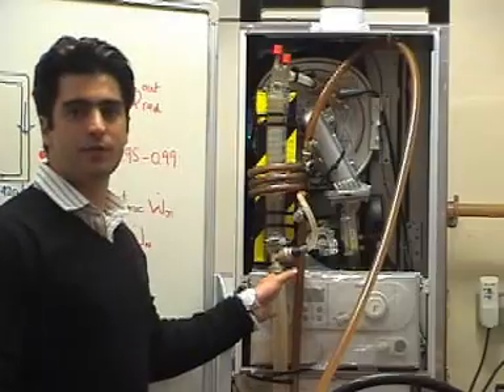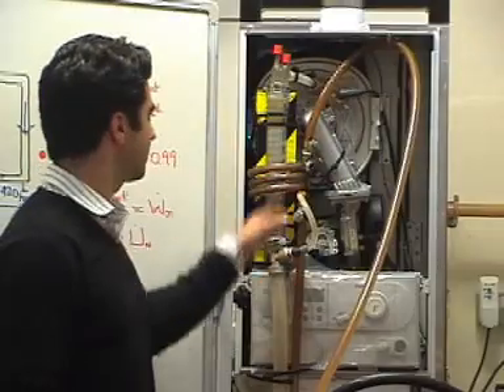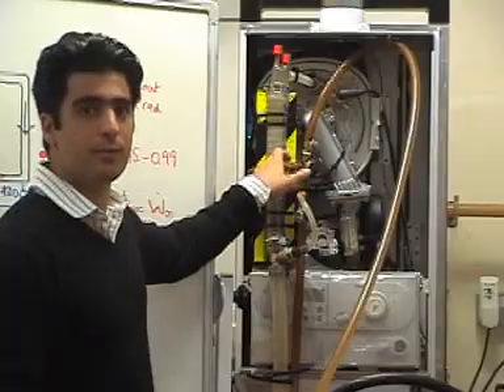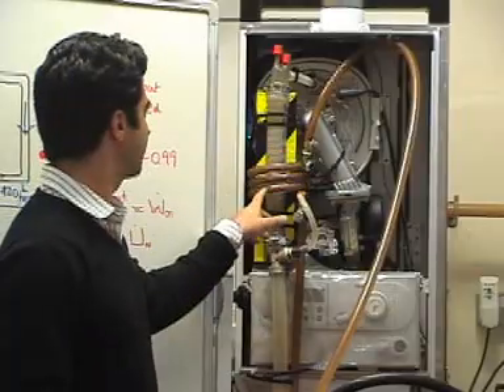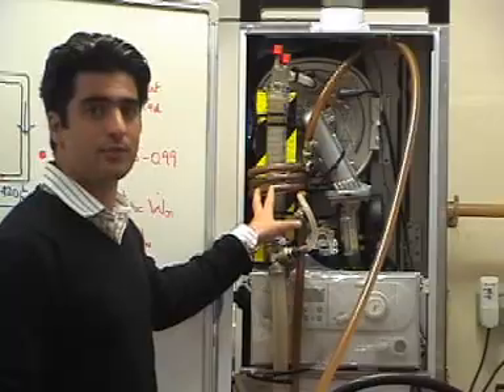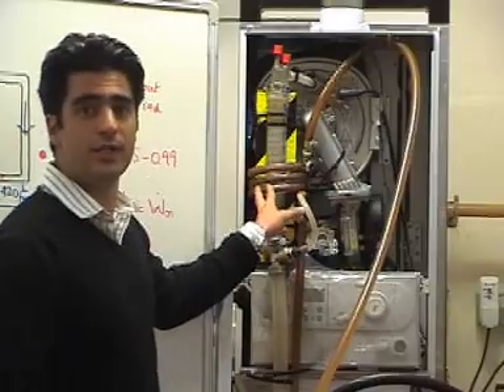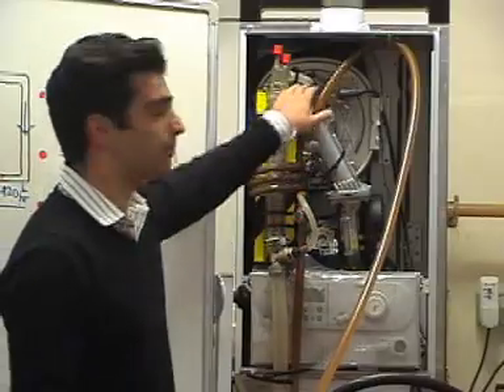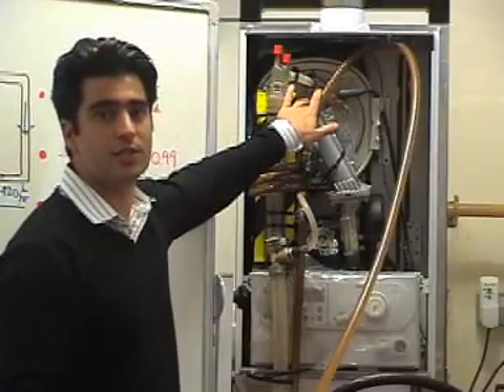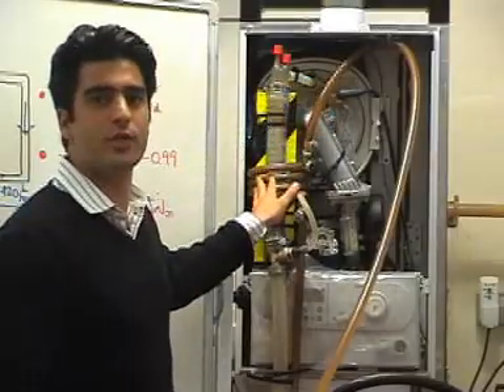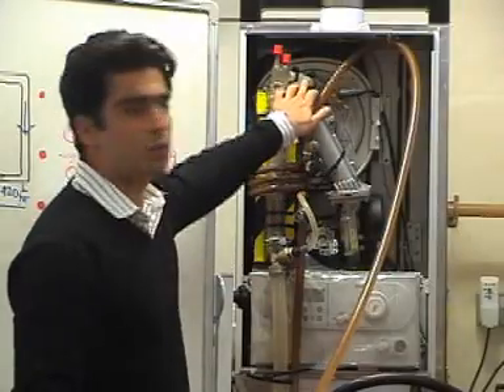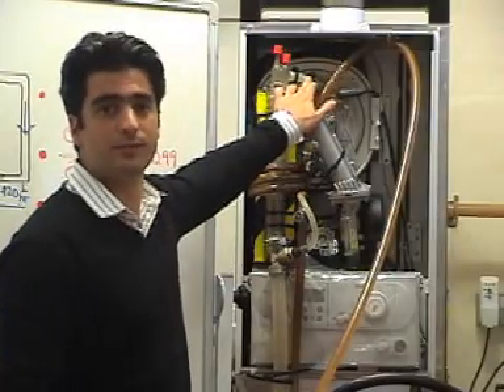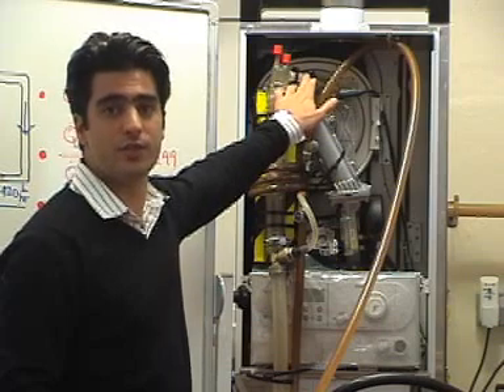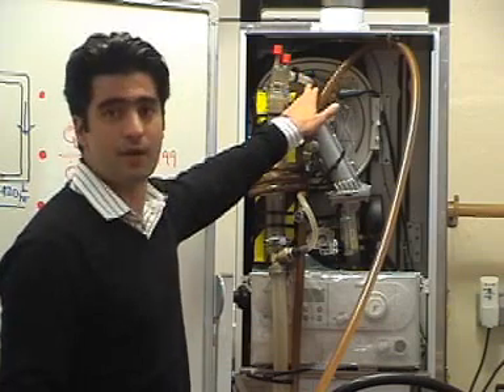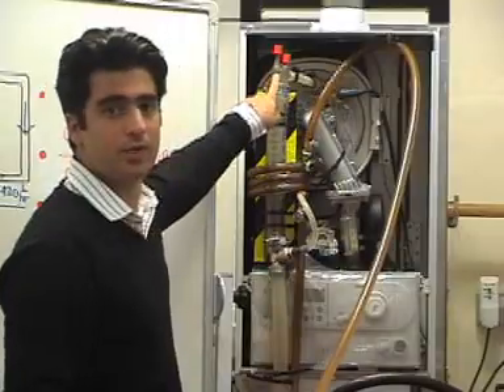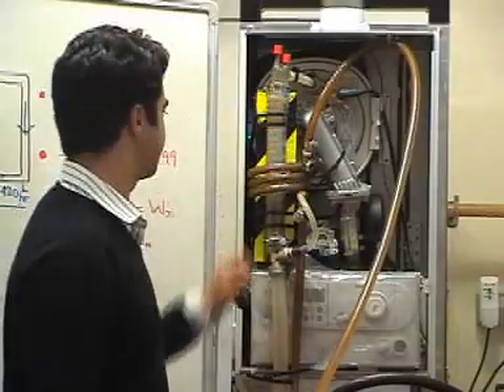The NIFTE pump consists of three main parts: the power cylinder that would normally be wrapped in insulation, the cold heat exchanger that's wrapped around the power cylinder, and a hot heat exchanger that is at this moment embedded inside the primary heat exchanger of the boiler. As soon as the burner is switched on, the working fluid, which in this case is water, in fact the same water that is being circulated to the radiators, evaporates. And when it evaporates, the pump is set in motion.